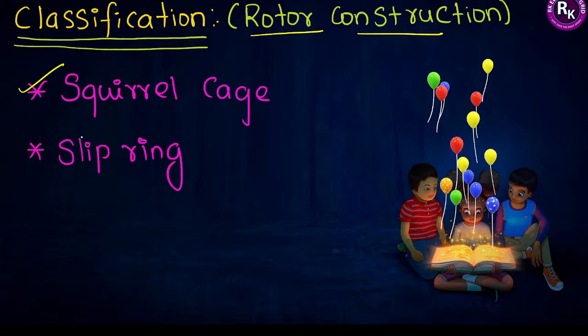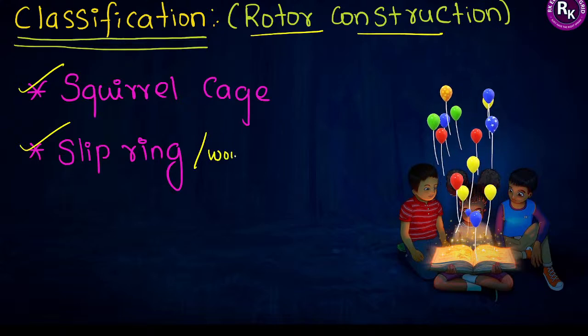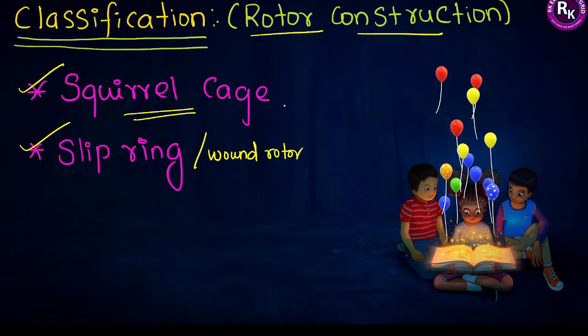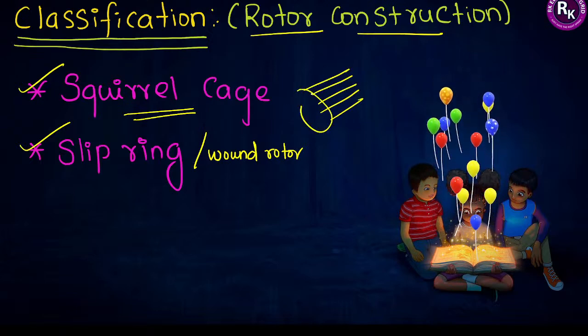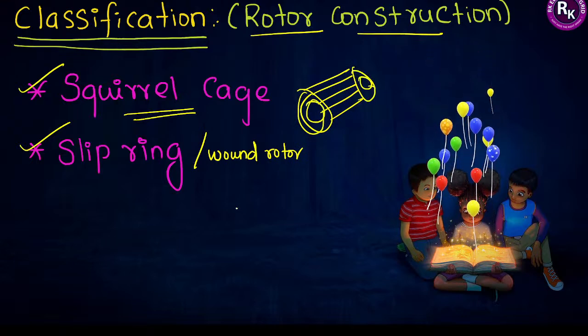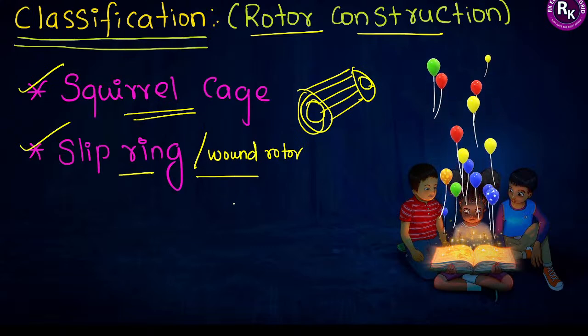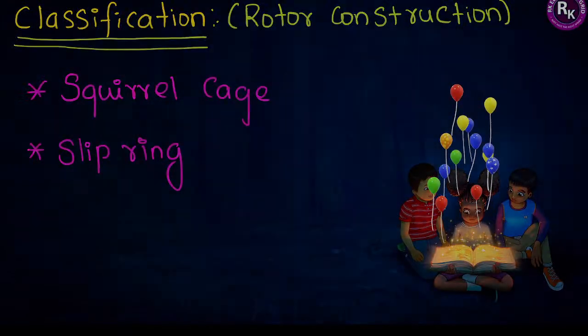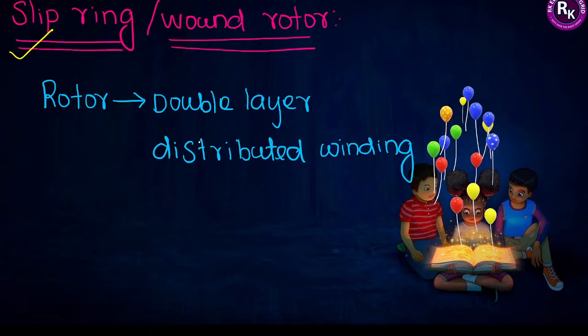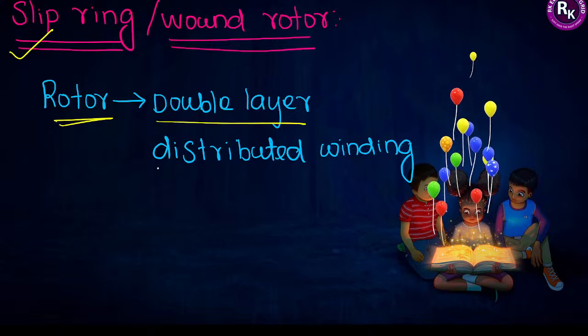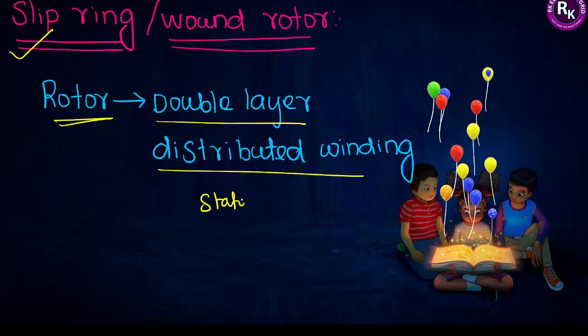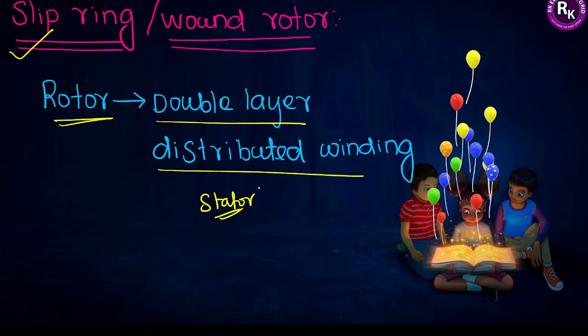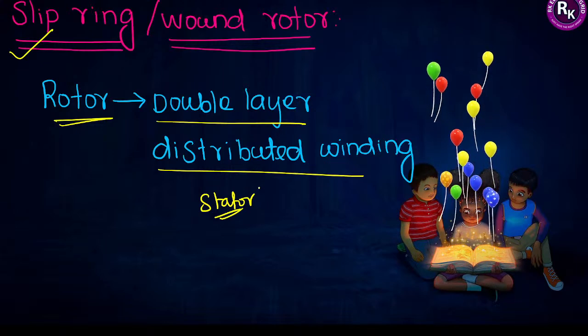Based on rotor structure, induction machines are classified into two types: squirrel cage induction motor and slip ring (wound rotor) induction motor. In the squirrel cage type, the rotor has copper bars that are short-circuited on both sides, inclined at a particular angle. In slip ring type, the stator and rotor structures are similar to each other — both designed with double-layer distributed winding. The number of phases and poles on stator and rotor are the same in the slip ring type.